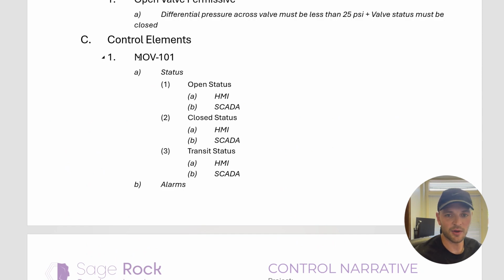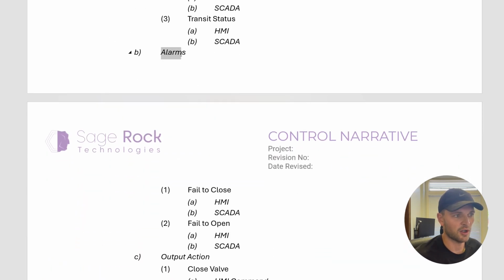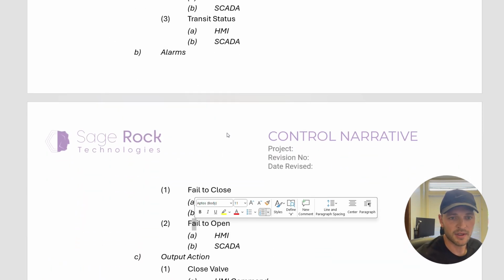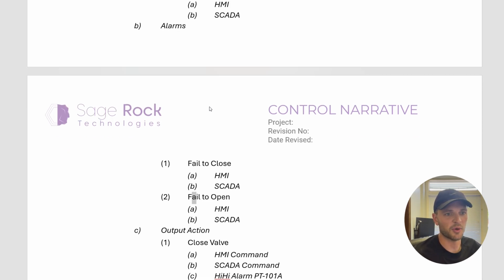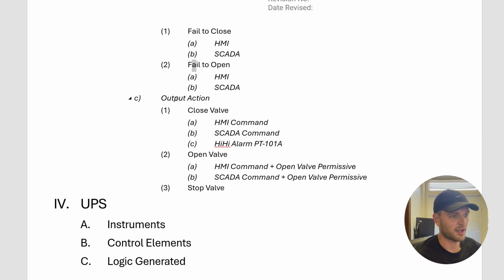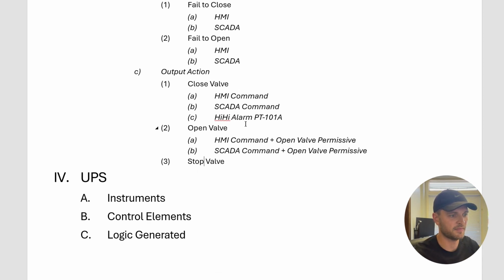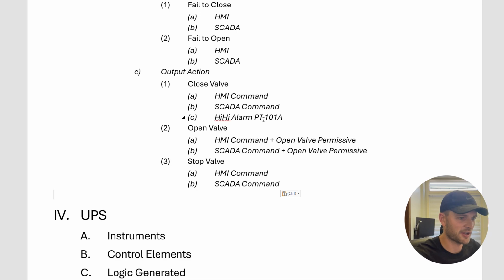Moving back up. So again, we have MOV 101 that also has status that we have to worry about, right? So we've got open status, closed status, and transit status, and these all need to be displayed on either HMI or SCADA in this case. Alarms, maybe we have a fail to close and a fail to open, right? And you might be able to define those a little bit more if you want to in here. And then again, we have our output action. So what can close this valve? An HMI command, a SCADA command, plus a high alarm on one of our pressure transmitters so we don't overpressure our pipeline in this case. And then we can also stop the valve. I'll add these right now. HMI command or SCADA command.